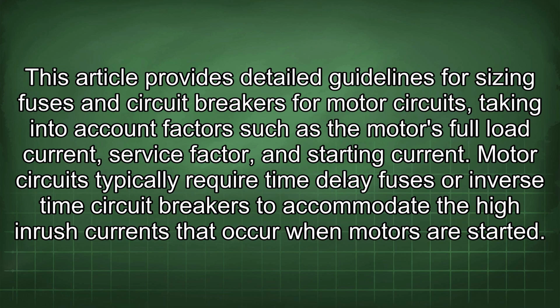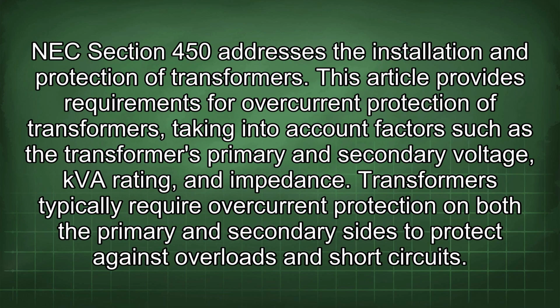when motors are started. NEC Section 450 addresses the installation and protection of transformers. This article provides requirements for overcurrent protection of transformers, taking into account factors such as the transformer's primary and secondary voltage, kVA rating, and impedance. Transformers typically require overcurrent protection on both the primary and secondary sides to protect against overloads and short circuits.